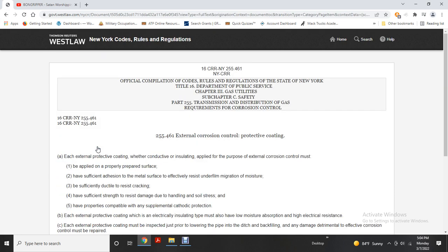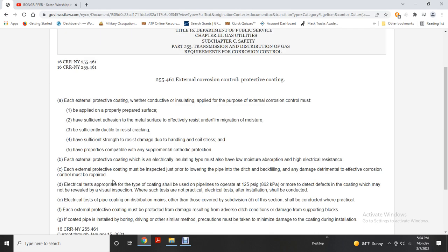Protective coating for external corrosion control must be applied to a properly prepared metal surface to effectively resist disbondment, should resist moisture, be sufficiently ductile to resist cracking, have sufficient strength to resist damage due to handling and soil stress, and have properties compatible with any supplemental cathodic protection. Each external protective coating of an electrically insulating type must have low moisture absorption and high electrical resistance. Each external protective coating must be inspected prior to lowering the pipe into the ditch, and any damage detrimental to effective corrosion control must be repaired.